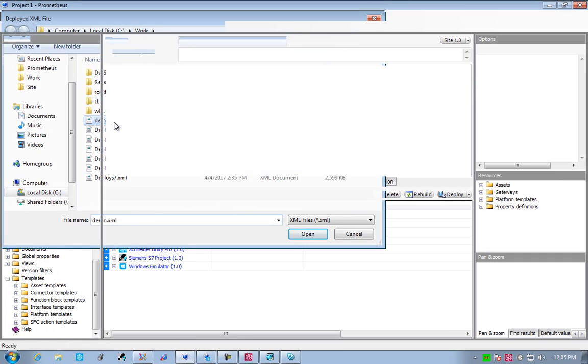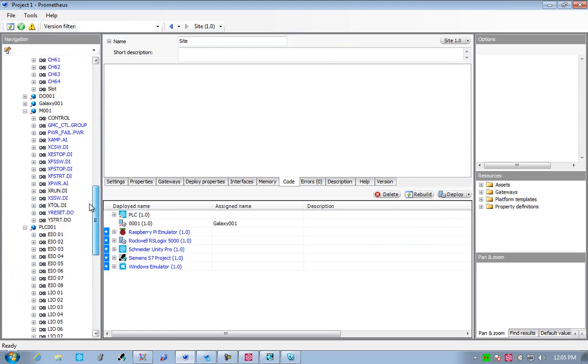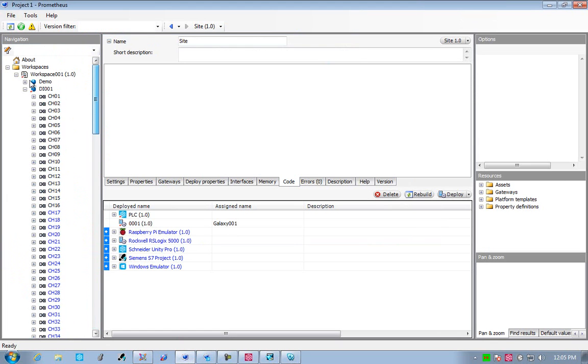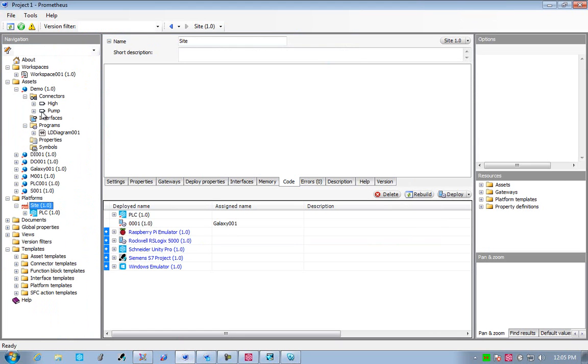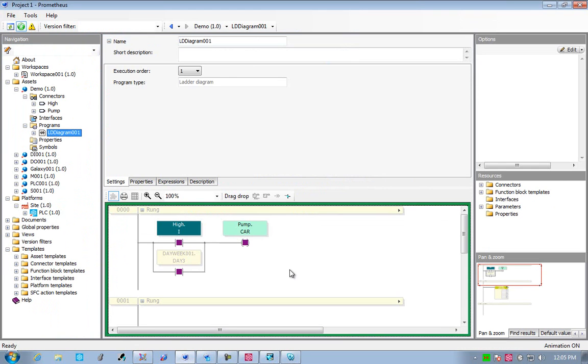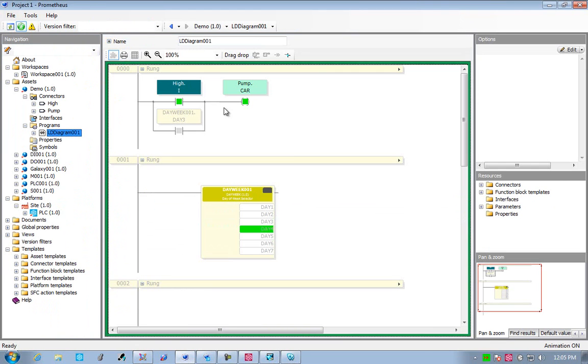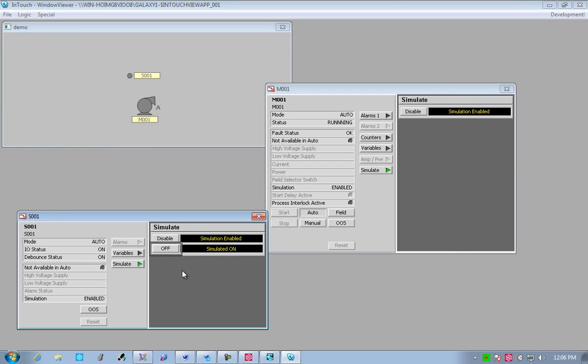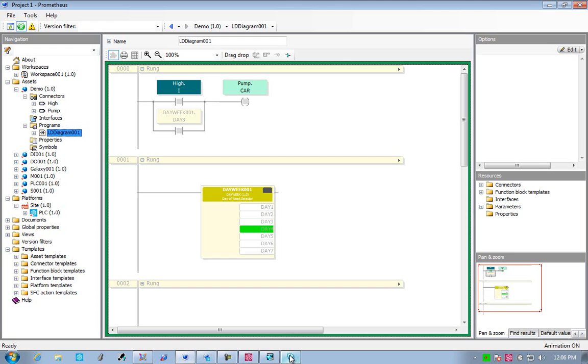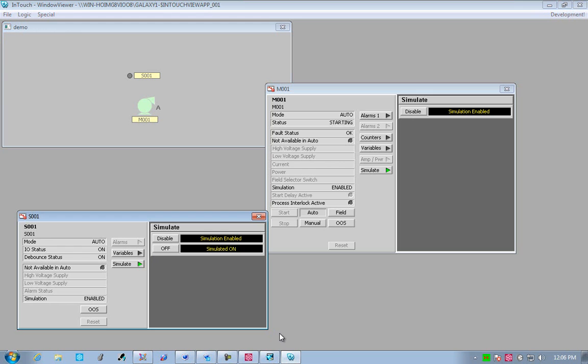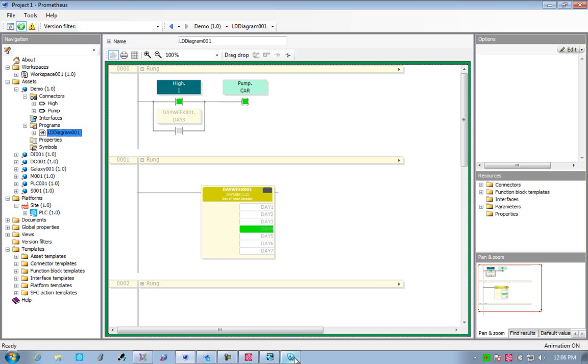We can also debug this from inside Prometheus. We want to be able to see this in the language it was written in, so that if there's an SOP or anything attached to it, we can actually see the logic executing the environment that we developed it in. Now we can see the logic here saying it's running because of the switch, not because of day of week three, because clearly we're not day of week three. Now if we went and turned it off, we would see that the animation is now off. We can see the direct response. We can even toggle variables and set information from within Prometheus, just like you'd expect in a debug environment.